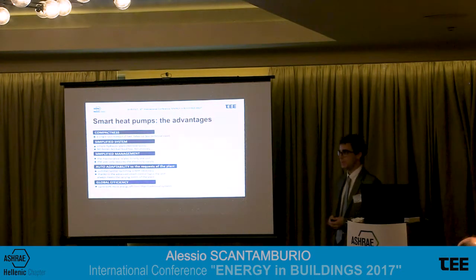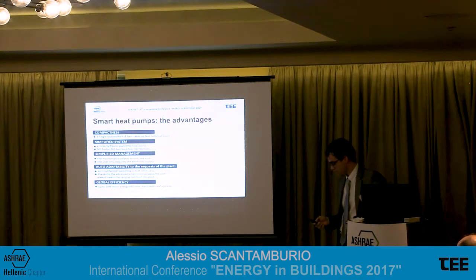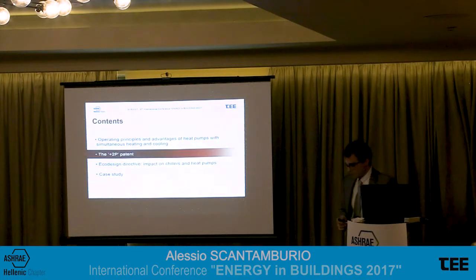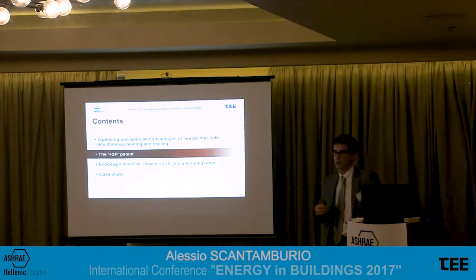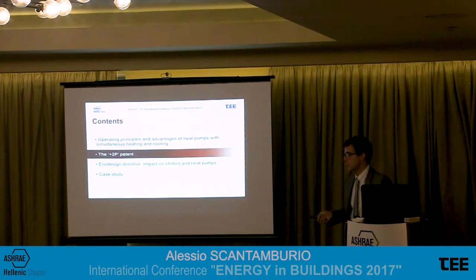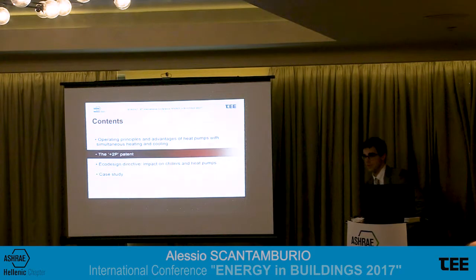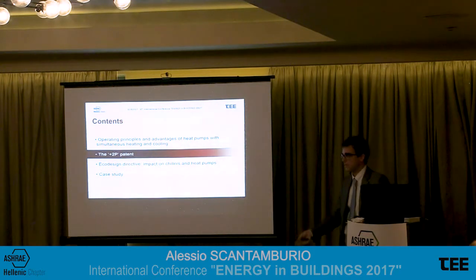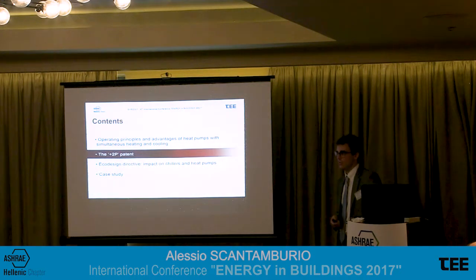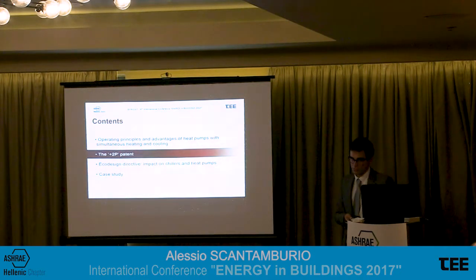And of course, the management is also simplified. Just think about the maintenance relating to one single unit, which is basically a heat pump. And the system is automatic, so you don't have to switch between summer and winter mode because every combination can be met. Surely when we have a gas boiler, we also have domestic hot water requests. The typical temperature of a standard heat pump is, I don't know, 45 to 50 degrees, more or less. So that is not enough for domestic hot water production.